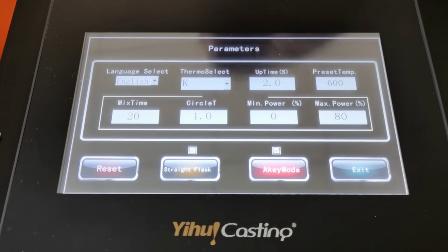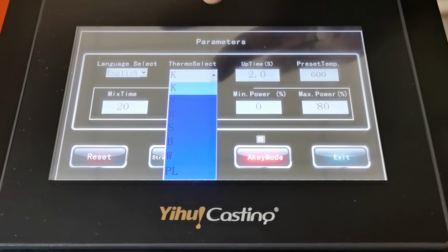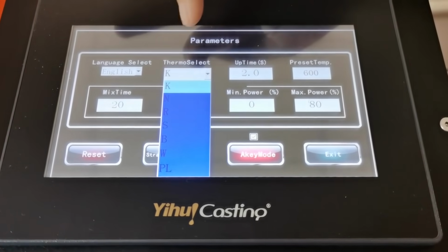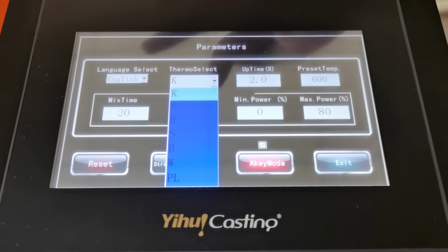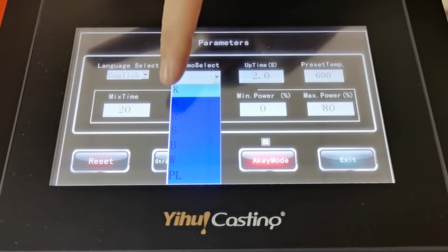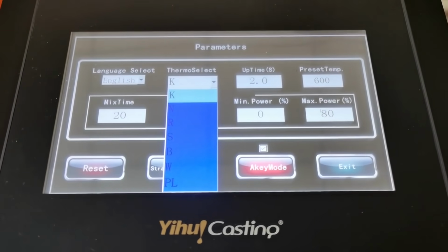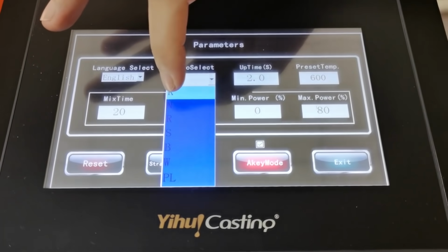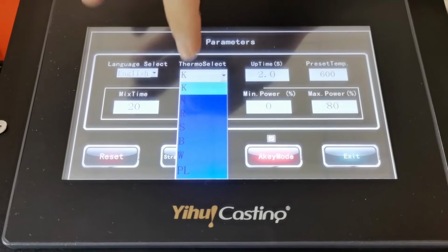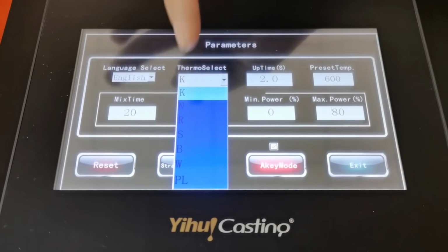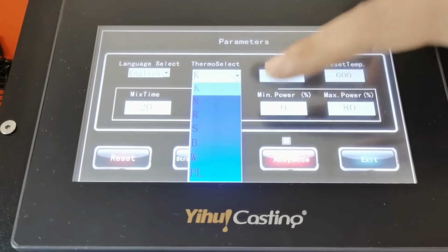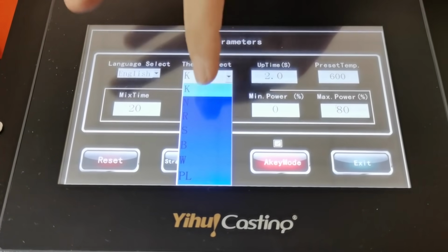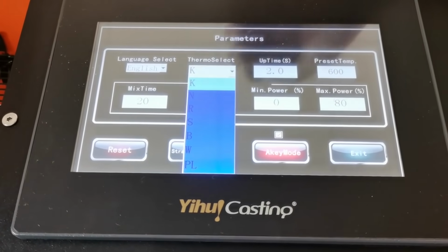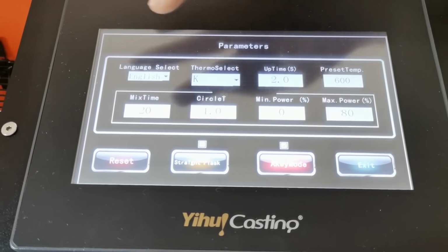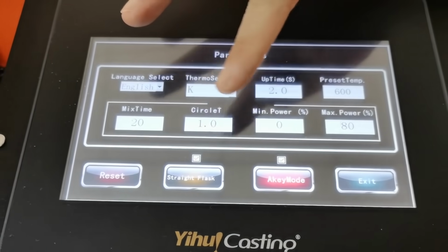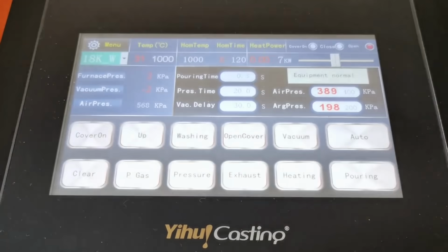Today we try English, so we select English. And thermal. We have different types of thermal as options. Please contact us before you order to make sure what type of thermal you use. Then select the correct one. Here we have the different types of thermal as options. Normally we use K, N, R, S. But if you use K or N, you can connect to the thermal connection K, because as I mentioned, it is marked at the thermal socket. If you use R or S, you can plug the thermal into the socket marked R. Today we try the machine with the K type thermal, so we tick K. The other parameters are not effective under the manual mode, so we ignore them. Then we exit parameter setting.